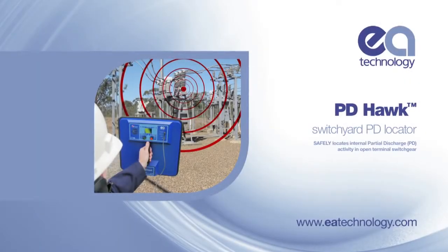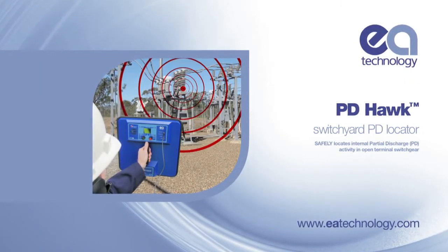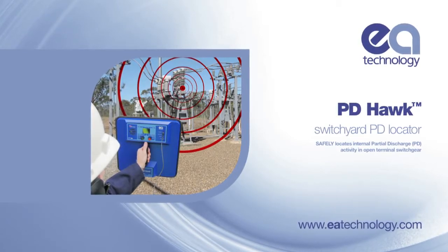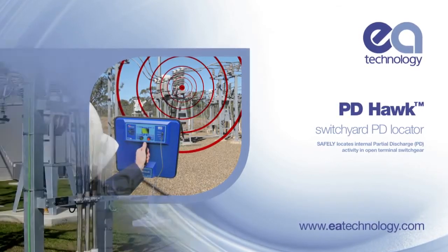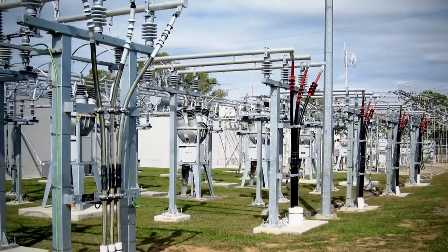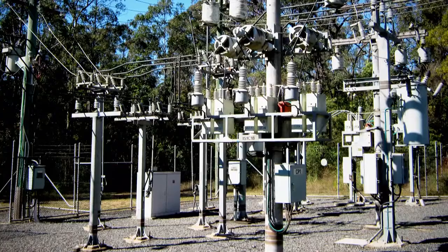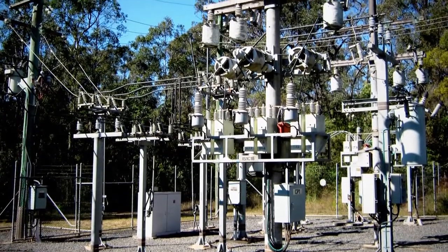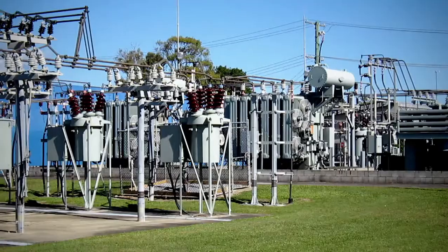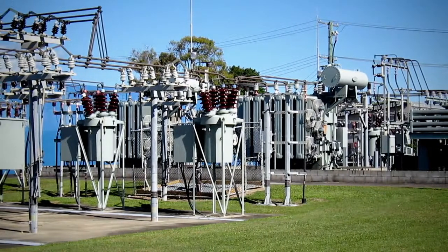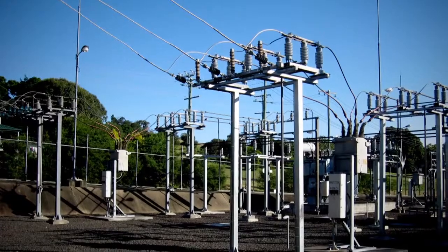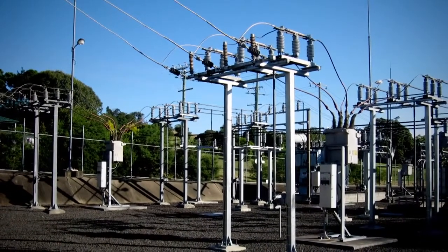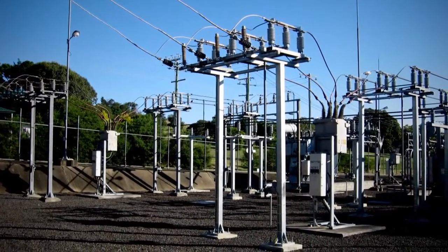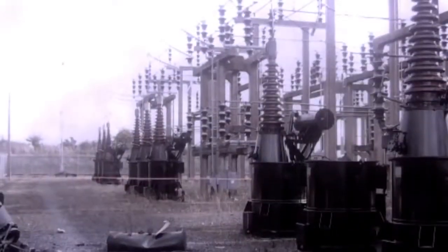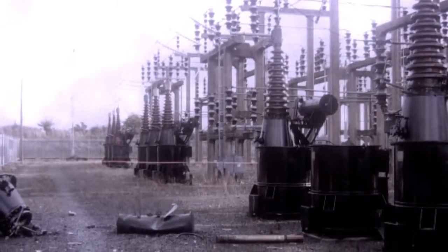The PD Hawk, the world's most effective instrument for locating partial discharge activity in distribution voltage switchyards. Because partial discharge activity, PD, is a sure sign of deterioration in switchyards, just as it is in substations. It can occur in assets such as instrument transformers, circuit breakers, disconnectors, cable sealing ends, and surge arresters, causing danger to people working in the switchyard and leading to flashover and failure.